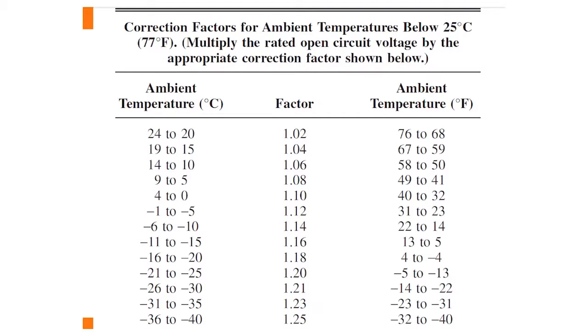Of course, there's the temperature correction factor table. Now it says, up to the 2014 code, that this table shall be used only when, essentially the way it's written, if you've got the correction factor coefficients, you have to use the coefficients. This is only used when you don't have the coefficients. Well, quite frankly, it's a very conservative table, and it's a very easy table to use. And so there's really no reason to require a calculation.